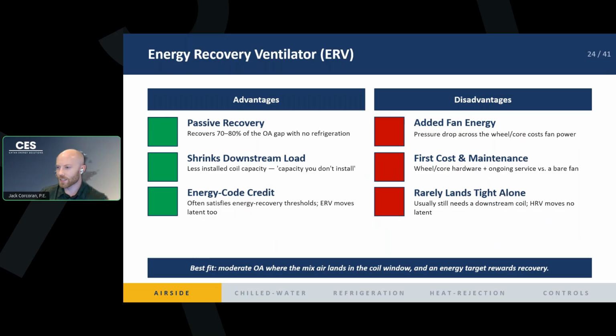And the last disadvantage is while it is free, right? It's great that it's free. It doesn't do a perfect job tempering the air. It only lowers it to like 81. I mean, if it's even hotter than 95 out, you're not going to get even 81. You might get 85 or higher. So you're still going to have to temper the air if you do have tight space temperature requirements and humidity requirements. It can't act on its own.